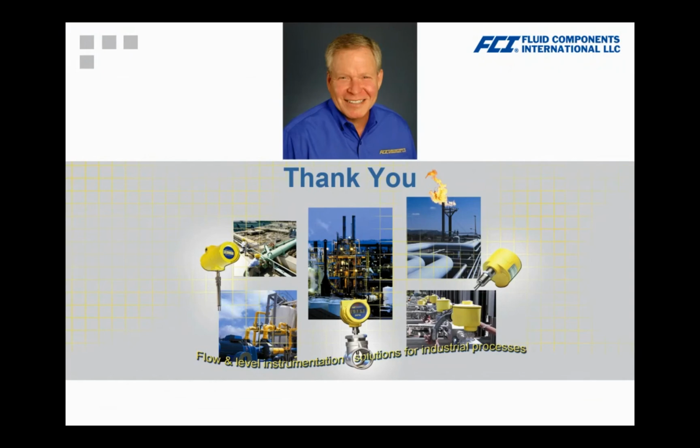Do you know the effective turndown of a Venturi tube? Venturi is typically, I believe, 8-to-1 or 10-to-1. All right. Can flow direction be calibrated in either direction, or can it be reversed by the installer? Yes, we can calibrate in either flow direction because we do have multiple calibration groups available. The error induced, again, is up to 1% if the flow direction does change.